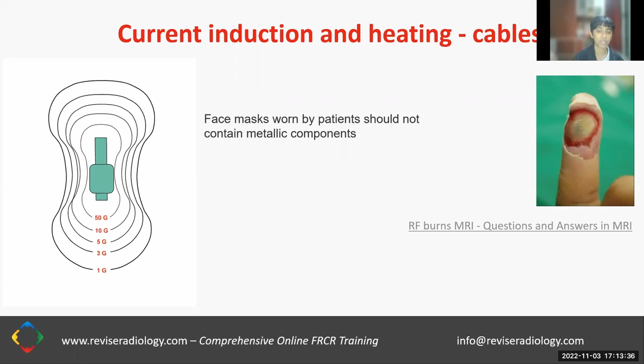There's a diagram on the left-hand side here, which shows the different types of magnetic fields and the various types of incidents that can occur. The big magnet creates a static magnetic field. The gradient coil creates the gradient magnetic field, and the radio frequency coil creates the radio frequency field. All of these fields can cause the malfunction of active devices. The static magnetic field causes translation and torque and projectile injury, due to metal implants and due to metallic objects outside the body. And the radio frequency field causes burns due to a number of phenomena, the chief of which is the resonant antenna effect.